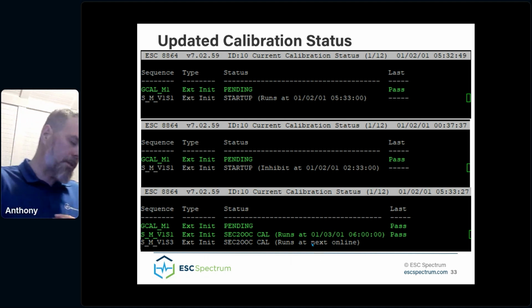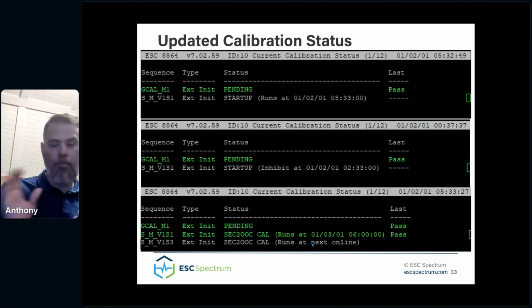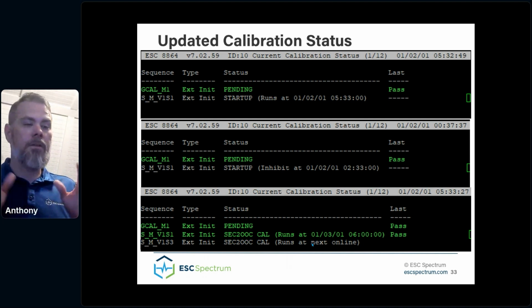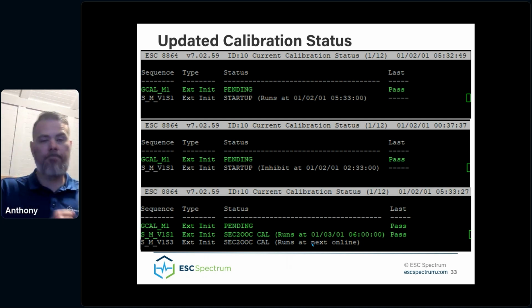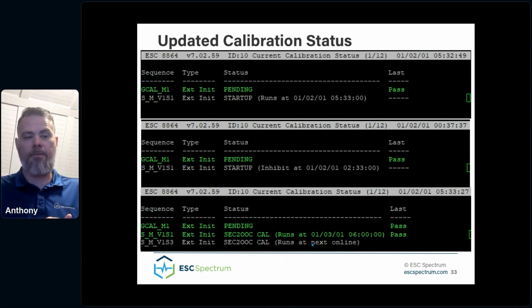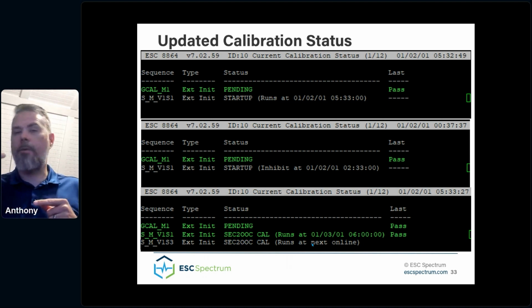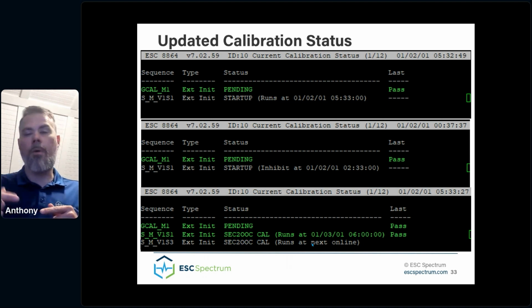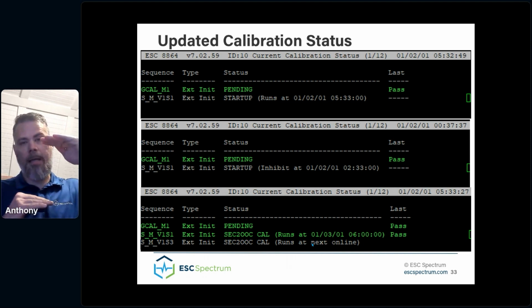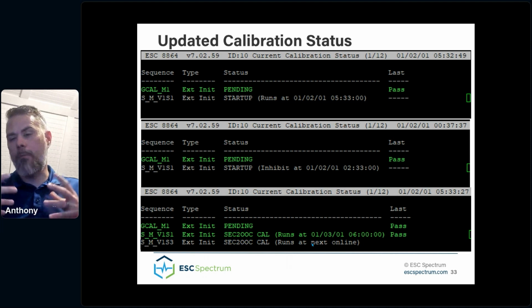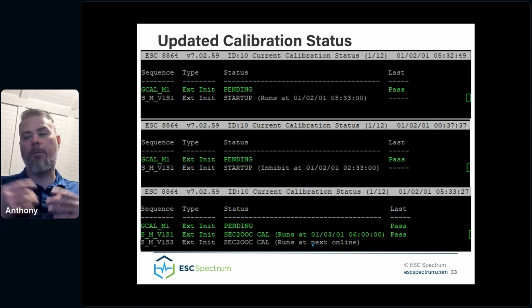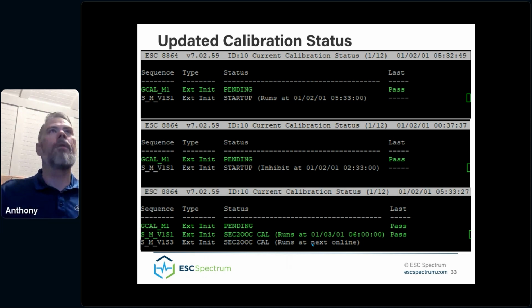Now, we did also add some stuff where if you abort the calibration for some reason, let's say you're running a sector OOC cal and you abort it, or the unit goes offline, something happens, the cal doesn't finish. We then disable the sector OOC cal settings for all of those channels that were affected by that calibration. That way, it's not constantly trying to run the sector OOC cal. When we disable that setting, it's documented in that calibration log that I demonstrated for the MDI. So you'll know when we re-enable them, that's also documented there. They're re-enabled the next time an online cal runs.